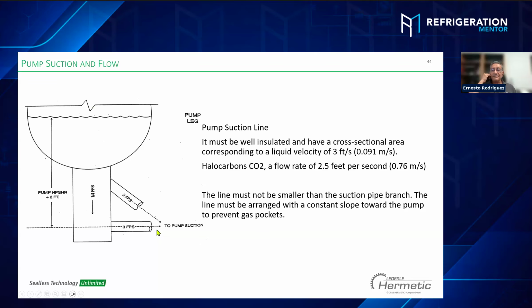Okay. You need to keep the velocity on the suction of the pump. For example, for ammonia, it's 3 feet per second, and for CO2, it's 2.5 feet per second. Why am I very specific on the suction? Well, when technicians are going to replace a pump and have problems, you need to be careful about the pipe diameter on the suction of the pump.